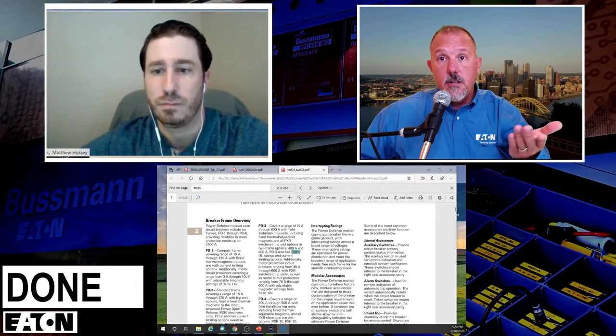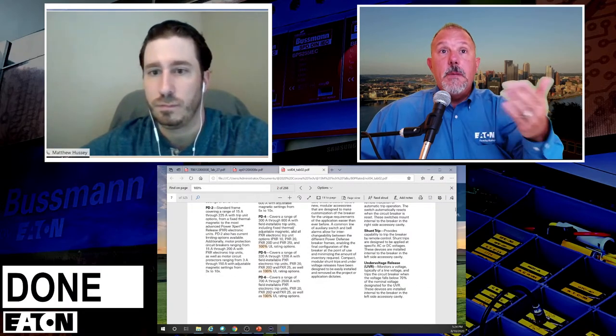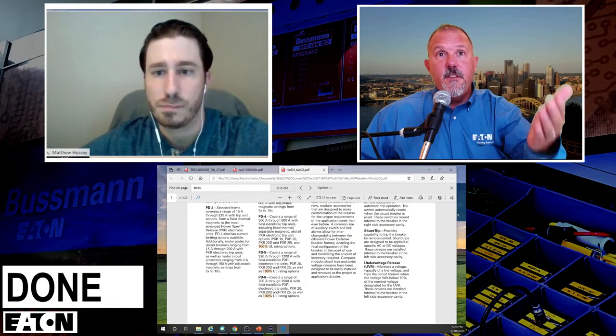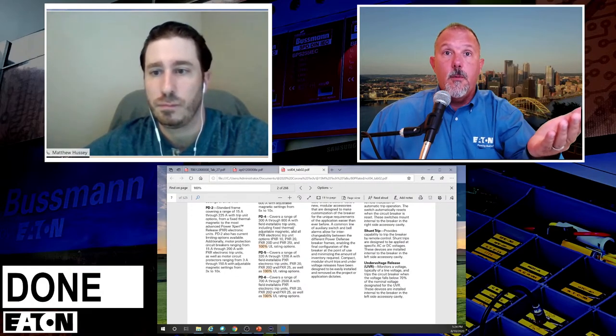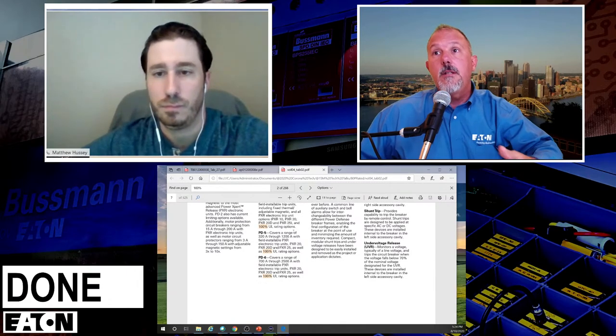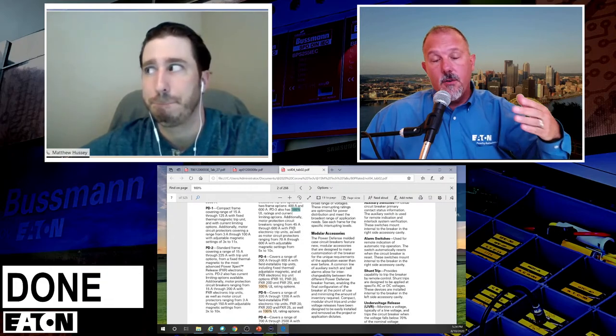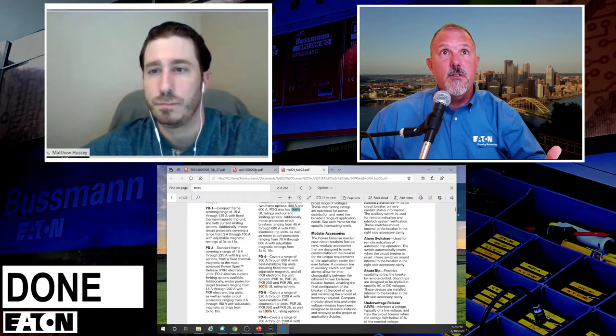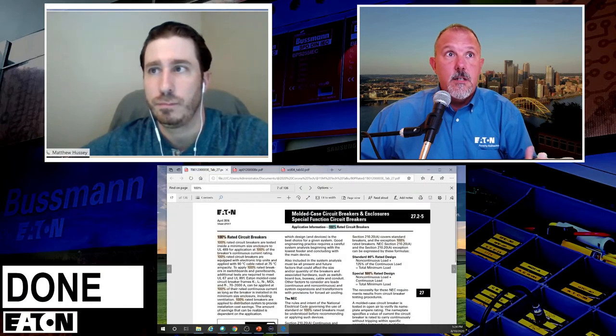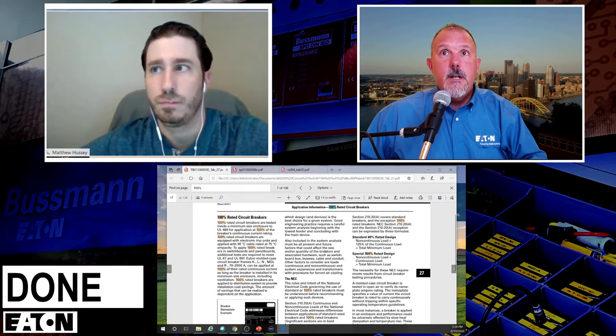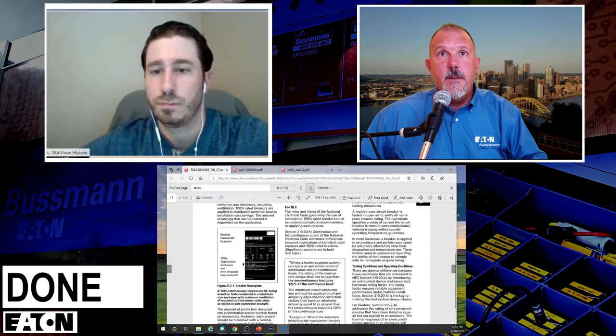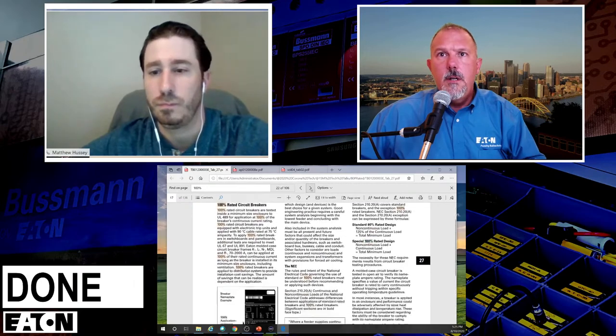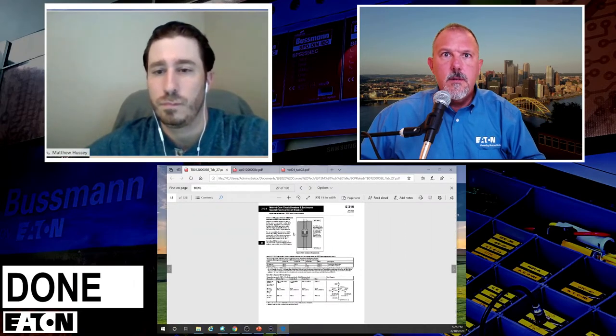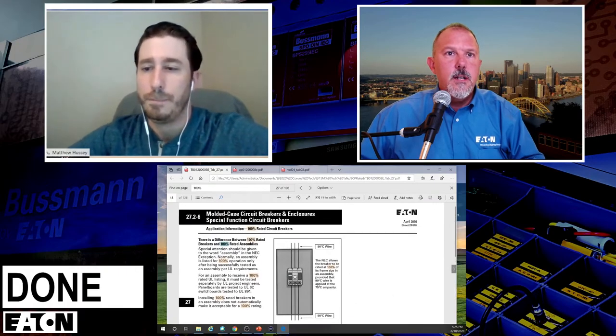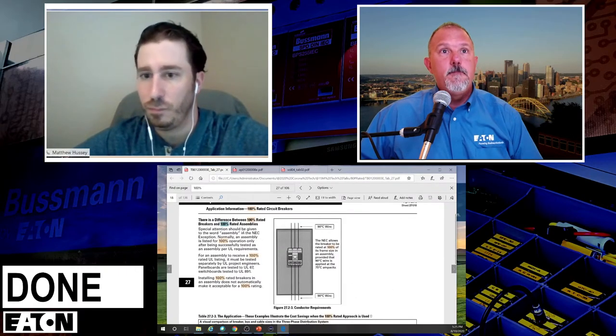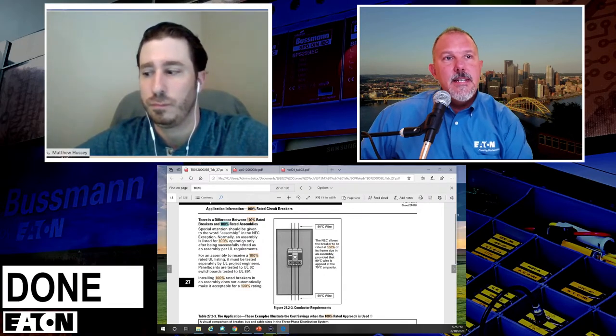Now, this is our molded case circuit breaker. It talks about our new PD, our new power defense circuit breakers, and that we have 100% UL rated options with electronic trip units. And again, no matter what manufacturer it is, not all of their circuit breakers are going to be able to be used in 100% rated applications. In this case, these are 100% rated devices. I was going to try to show panel boards. Here we go. What's this one? The difference between 100% rated breakers and 100% rated assemblies. Normally, an assembly is listed for 100% operation only.